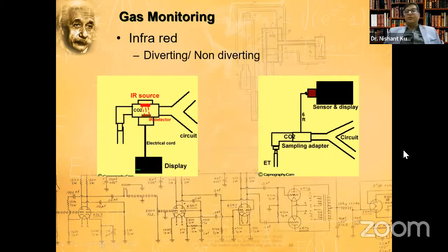Okay, ETCO2. It is often said that if you have the choice of all the monitors and you can have only one monitor, the one monitor that you would like to have is an ETCO2 or gas monitor. Now, we know that we have the mainstream sensors and the sidestream sensors. There are three principles which are used to measure the gases. Now, infrared can be diverting or non-diverting. As I said, non-diverting is the mainstream, diverting is the sidestream one.